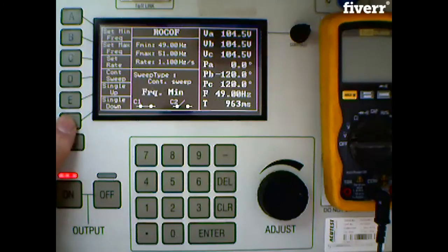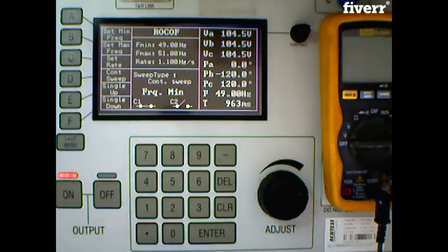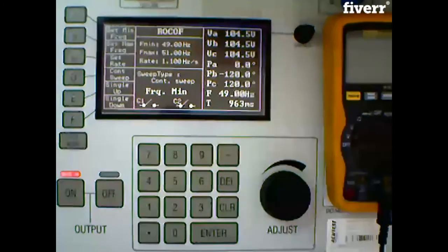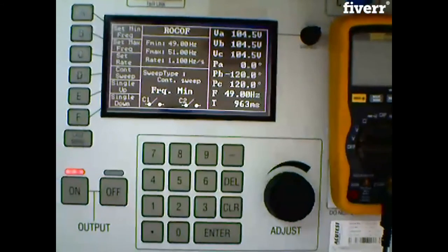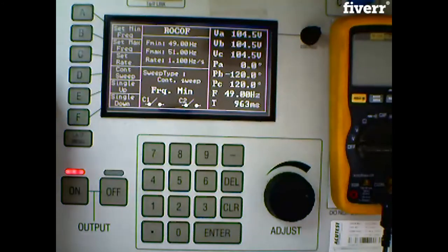It trips at 963. That's absolutely perfect. So our down, we can write into our box, 963. We're now down, so we can now do our increasing frequency, which is our up setting. And it comes at 992.